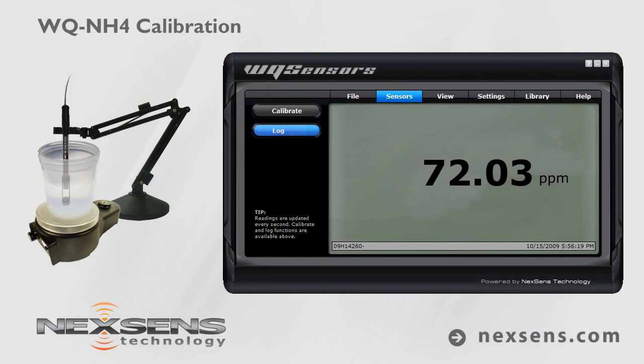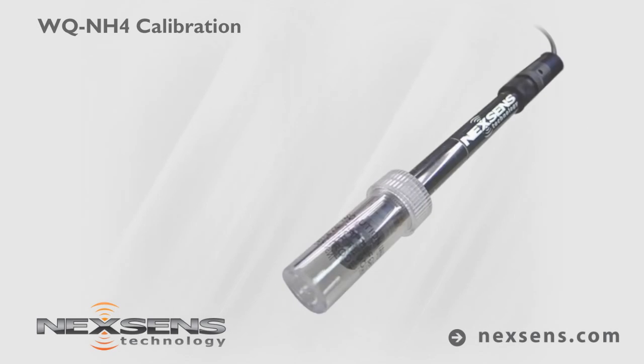Quality data collection requires frequent calibration. For best results, calibrate before each use. When not in use, the WQ ammonium sensor should be stored in the bottle in which it was shipped. NexSens WQ sensors — the latest in smart sensor technology.